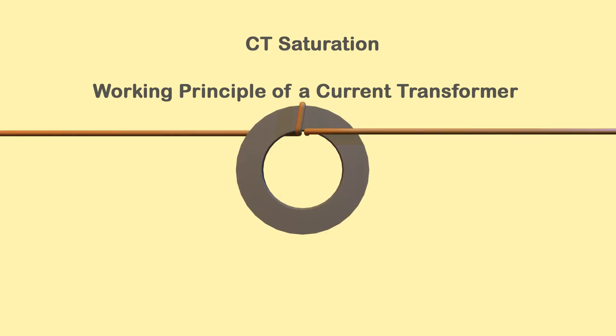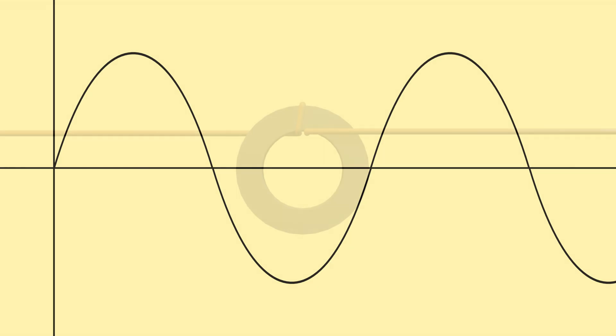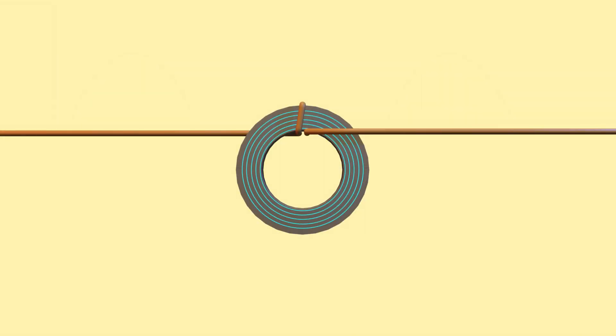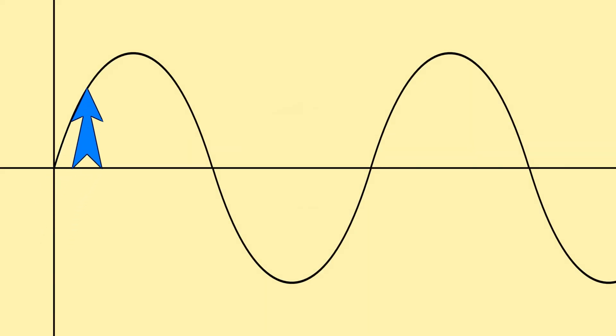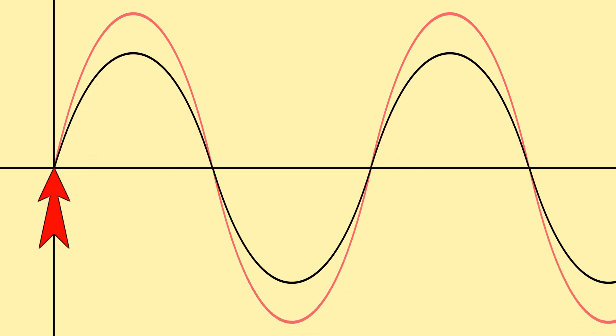When we connect the CT primary in series with the load line, the current flowing through the CT primary is nothing but the current in the load line or the electrical line. Now suppose the load line carries a pure sinusoidal current — that means the CT primary current is pure sinusoidal. This current creates a magnetic field in the CT core which in turn produces magnetic flux in the core. As the current increases, the flux also increases, and when the current decreases, the flux also decreases. So the flux due to the primary current follows the waveform of the CT primary current, and it also has a pure sinusoidal waveform.